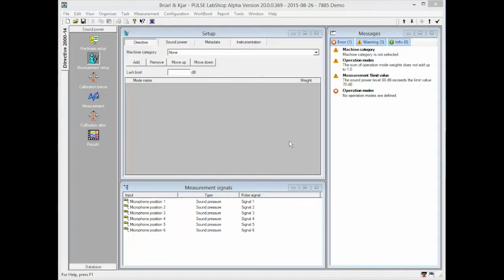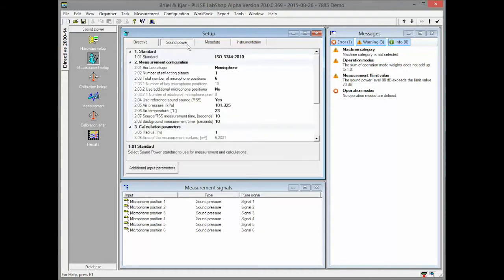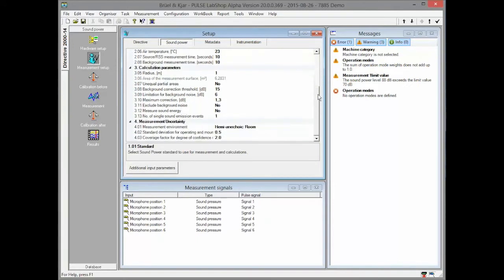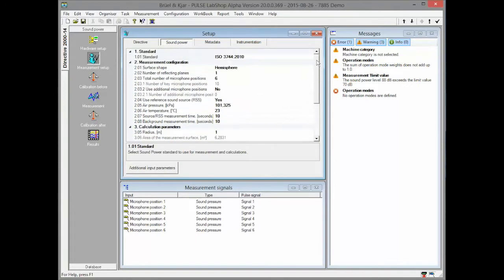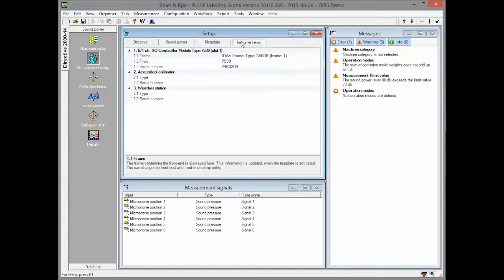The setup is divided into four tabs. The first one contains the configuration of the measurement according to Directive 2000. The second tab contains the setup for the underlying sound power standard. The third tab contains the metadata and the information about the used instrumentation is automatically gathered in the last tab.